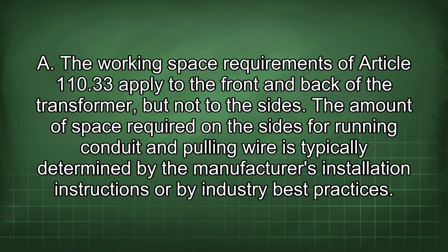The working space requirements of Article 110.33 apply to the front and back of the transformer, but not to the sides. The amount of space required on the sides for running conduit and pulling wire is typically determined by the manufacturer's installation instructions or by industry best practices.